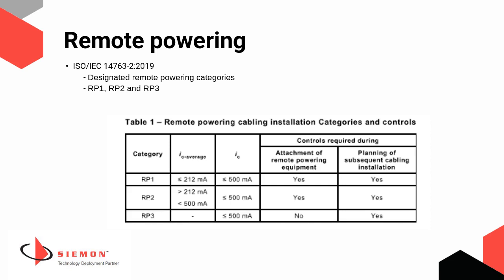For category RP2, attachment of the remote powering equipment at a distributor is controlled such that the average current for all conductors served by the distributor is restricted to a specified value between 212 milliamps and 500 milliamps. For category RP3, attachment of the remote powering equipment at a distributor is unrestricted, subject to the limit of less than 500 milliamps. In terms of planning and installation practices, the following apply.